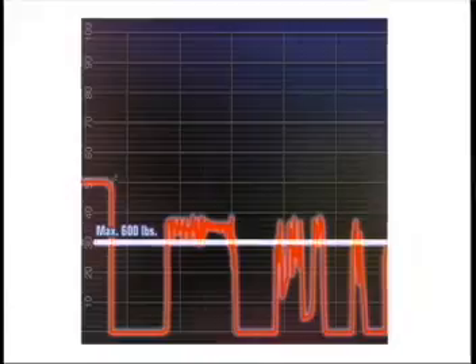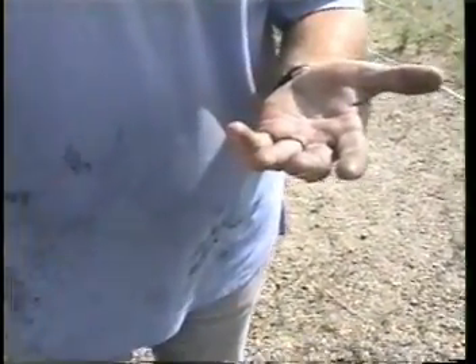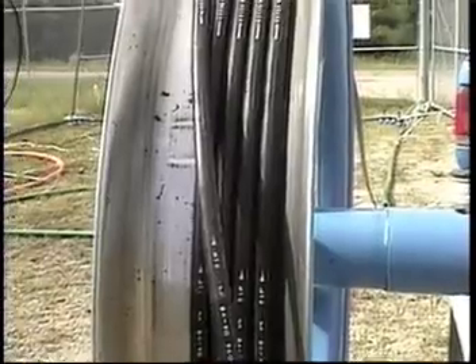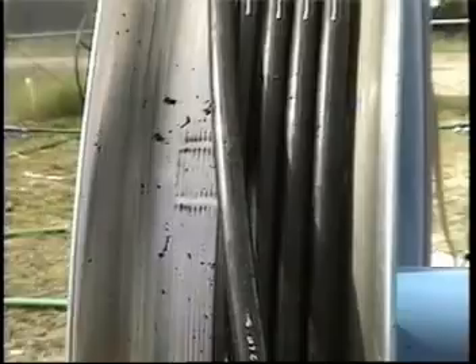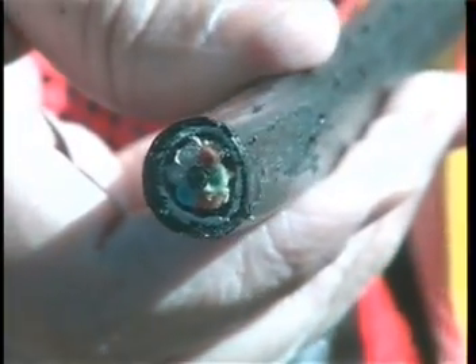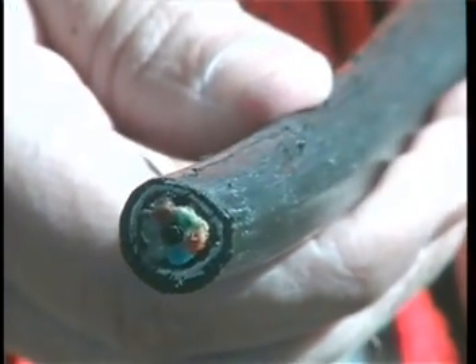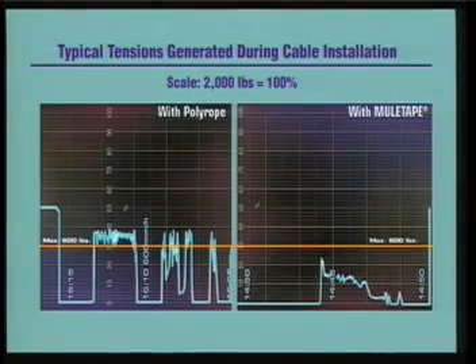The results of our experiment were conclusive. Use polyrope to pull fiber optic cable and you'll get burned. Not only do you risk stripping the cable jacket, you risk cable failure due to microbending and crushed fibers. Records from the tension meter clearly indicate that the cable pulled with the rope was subjected to more than 600 pounds of tension several times during the pull. That's well over the cable manufacturer's installation specifications.